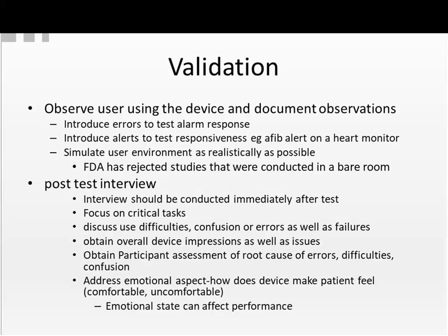For instance, an afib alert on a heart monitor. We're going to simulate the user environment as realistically as possible. Now, that's an important point because the FDA has rejected studies that were conducted in a bare room where there was no attempt to simulate the user environment.